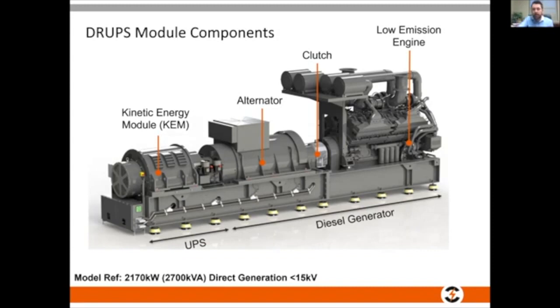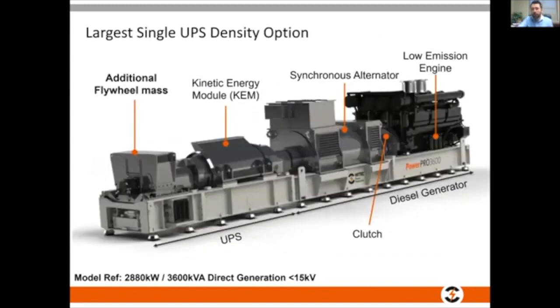Now, if you need more than 2.2 megawatts, we can do it. In fact, Drups offers the highest single power density UPS in the world, which is 2.88 megawatts. I show you here. So 2.9 megawatts. Let's round it off. 3.6 MVA. Again, anything up to 15 kV. Now this one looks slightly bigger. The visual doesn't do it justice.